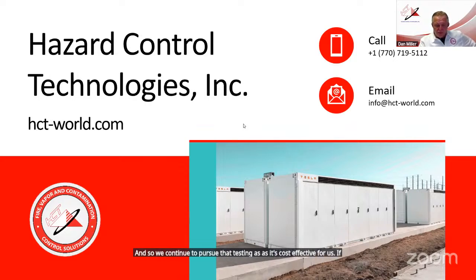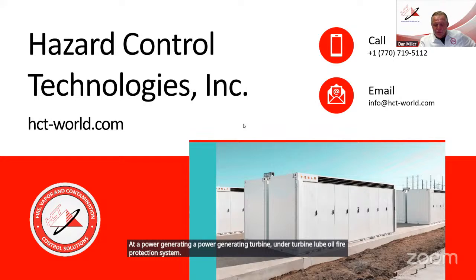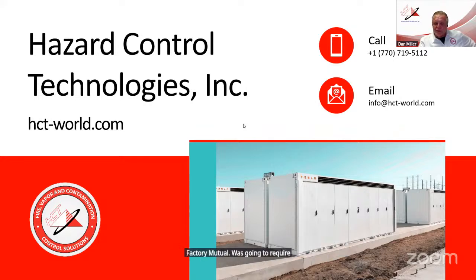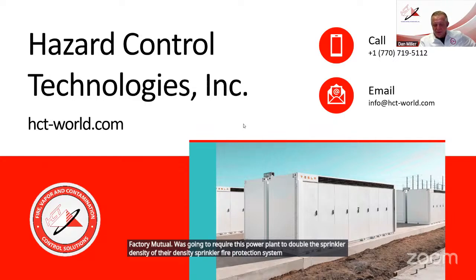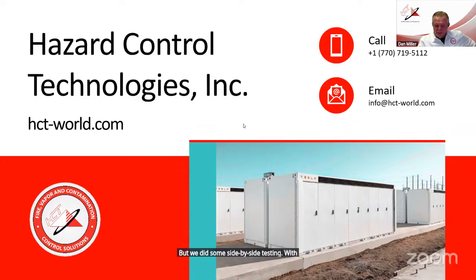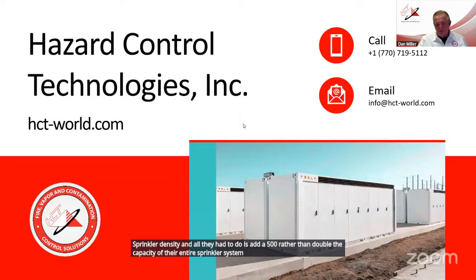Here's an example: at a power generating plant's turbine lube oil fire protection system, Factory Mutual was going to require the plant to double the sprinkler density of their fire protection system using plain water because they didn't think it was adequate. But we did side-by-side testing with FM witnessing, and F500 was able to control the fire very well at their current sprinkler density. All they had to do was add F500 rather than double the capacity of their entire sprinkler system, saving millions of dollars. FM approved that, but only for that specific site.